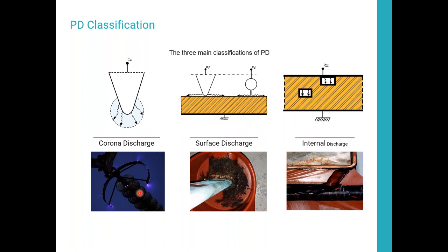And you can detect corona discharge in your medium voltage gear, and upon inspection, see that you are having a breakdown that's going to eventually lead to partial discharge. So while it's not as critical as surface and internal discharge in medium voltage equipment, it is a concern. If it's detected during testing, it should be noted for inspection in the future and monitored, because it will possibly develop into future partial discharge, or it can be causing damage that will cause an outage in the future. So it's one of those things. In medium voltage gear, you want to note it, you want to recognize it, and when you can, on a maintenance cycle, see if you can mitigate, clean up whatever the cause is. And we've got some pictures of some corona discharge in medium voltage gear where you see it starting to break down to the point where partial discharge is going to start. So we've got an example.